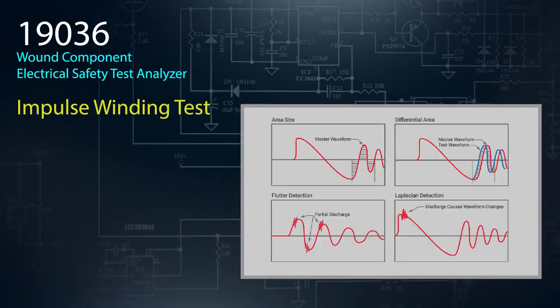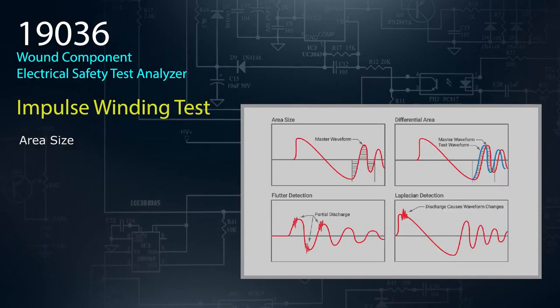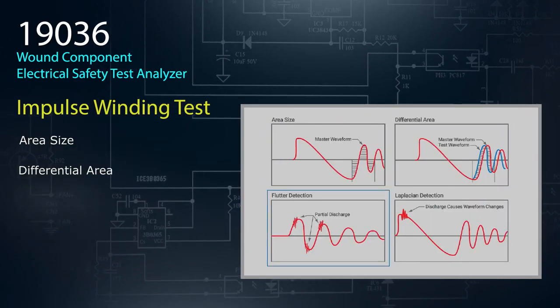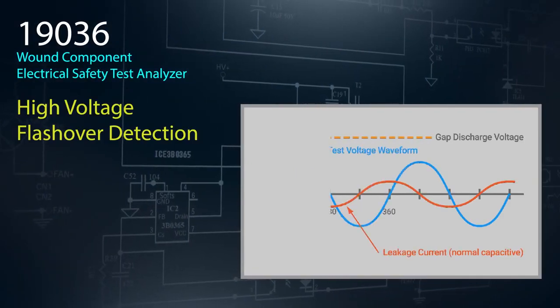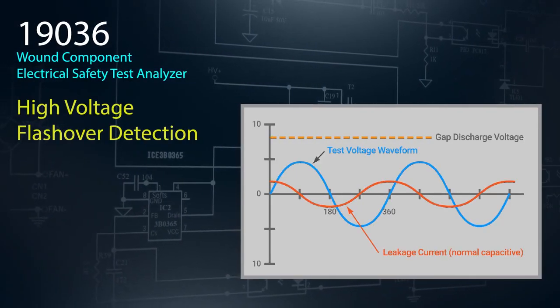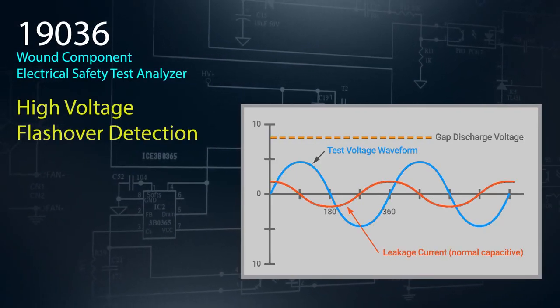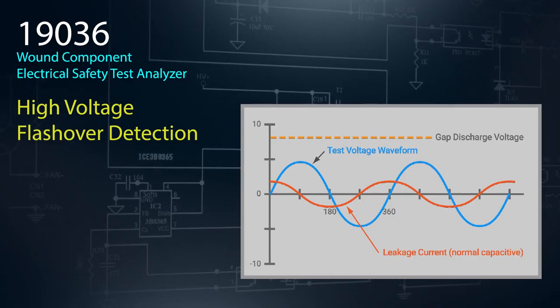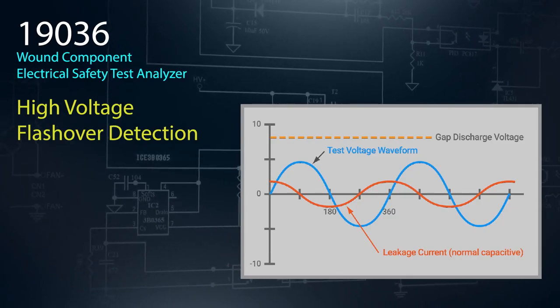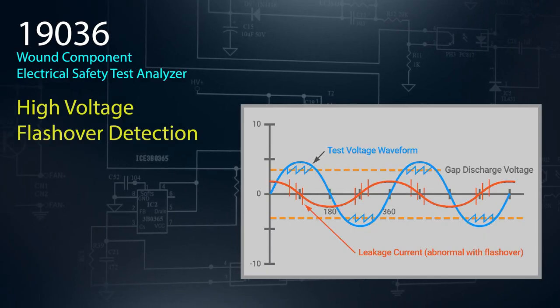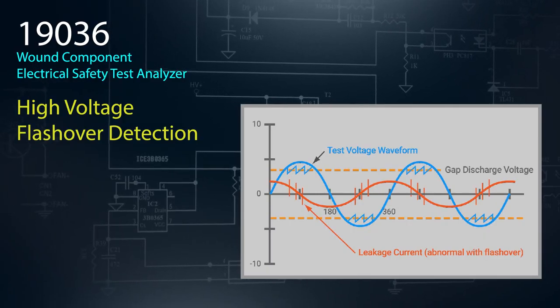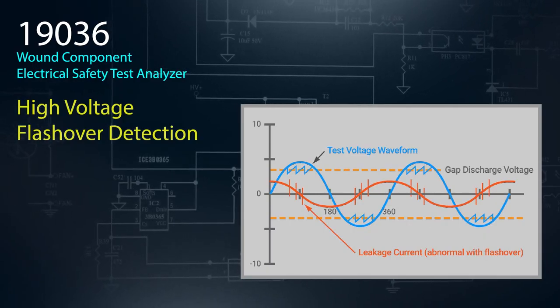Data of the impulse test can be analyzed by area size, differential area, flutter value, or by Laplacian method. Included is flashover detection. During high-voltage testing, the 19036 is able to detect any high-voltage electric shorts made through the air between exposed conductors. Since flashover cannot be detected by leakage current RMS value, this additional test is a valuable feature of the 19036.